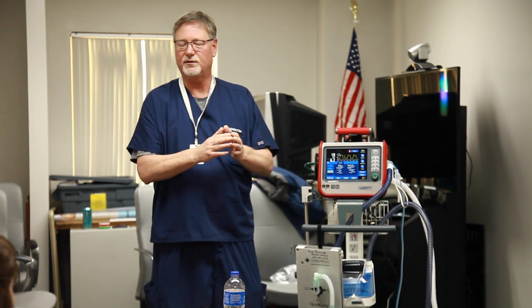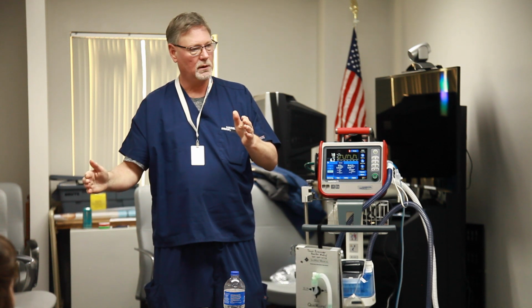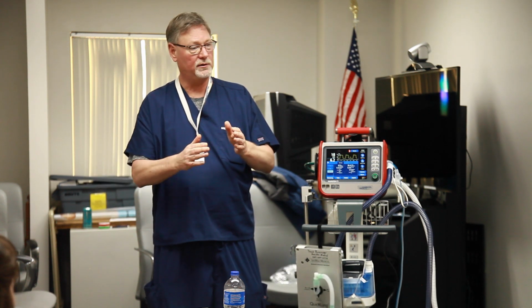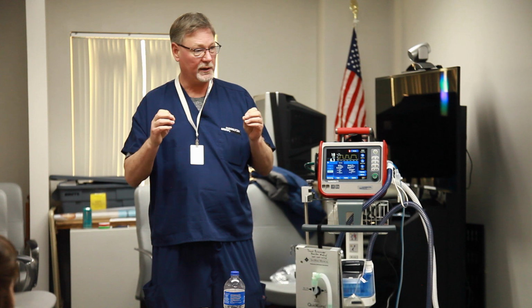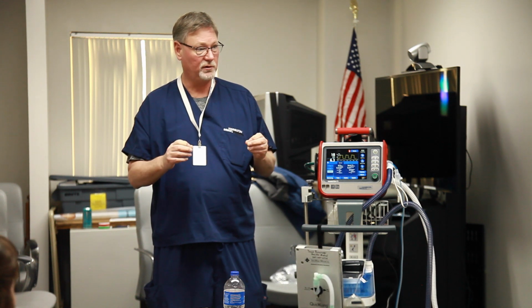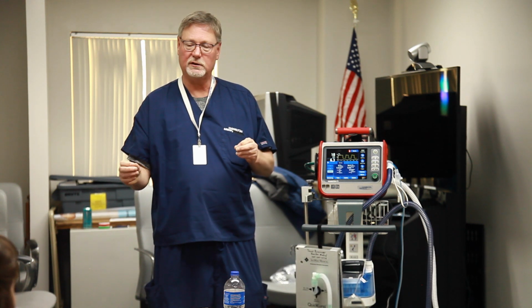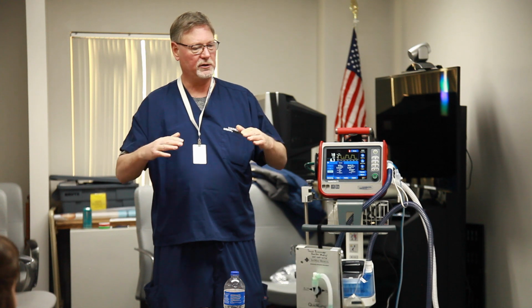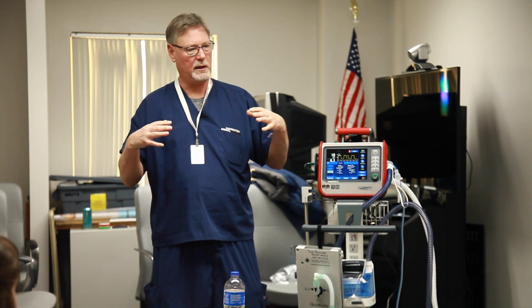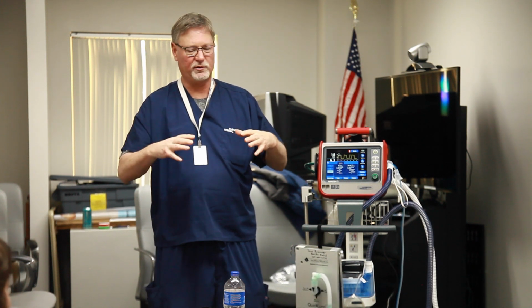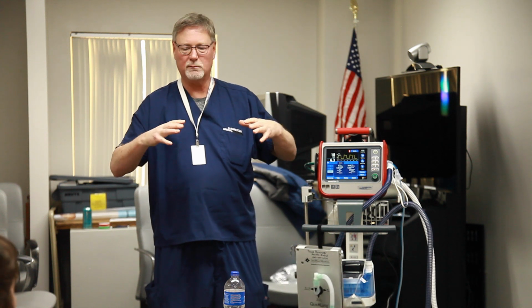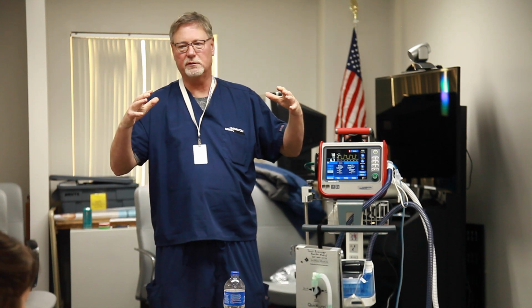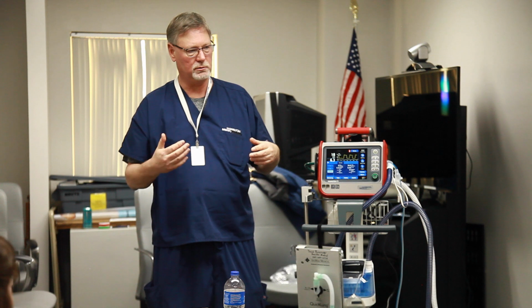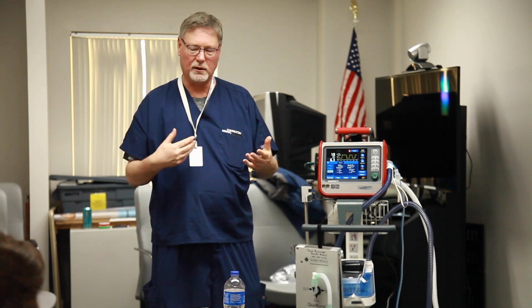They have a time constant that's very long. And it's going to say, oh, I need to exhale, because it's looking at expiratory time first. And it's adjusting the respiratory rate according to that, because it knows if I can't exhale, I'm going to be trapping, just like what she said. I'm going to be just adding more air on top of air, and I'm never going to be able to get it out. So I know that's an issue. So it's doing all these calculations in itself.